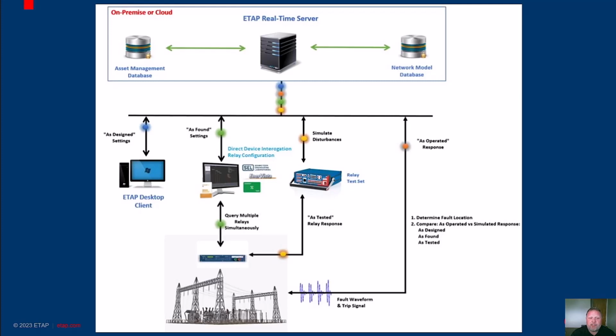If you've attended any of my presentations on AFAS or eProtect before, you're likely familiar with this image. It highlights the crucial role that AFAS plays throughout the entire life cycle of a relay. First, we use the ETAP desktop client to model the electrical system and ensure that the as-designed settings are accurate. To validate these settings, we employ STAR and STAR-Z for protection and coordination studies, which ensures reliability and efficient protection of your system. Next, we can seamlessly integrate with the relay's software to download the as-found settings in the field, eliminating the need for manual data entry and reducing the risk of human error. This enables us to identify any discrepancies between the validated as-designed settings and the actual as-found settings, ensuring the proper functioning of the relays and maximizing system uptime.